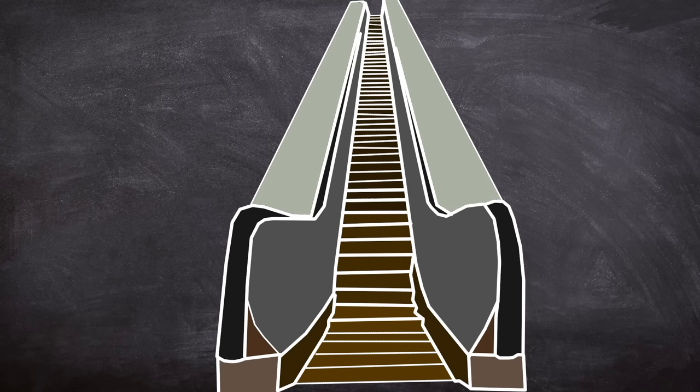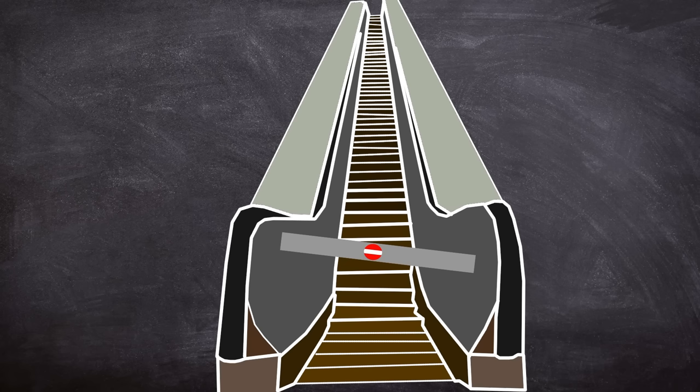The now smoking escalator 4 was taped off, but members of the public continued to step over and continue on the unmoving escalator steps. BTP officers reported the fire as mainly on one side and stretching about half way across the width of the escalator, over one or two steps. The fire was burning cleanly with flames about handrail height.